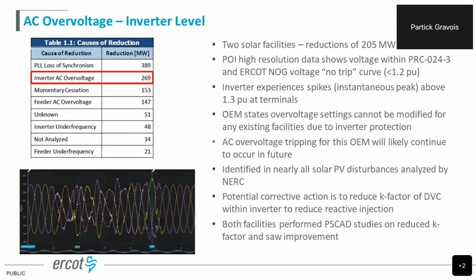The next was the inverter AC overvoltage. This one is a little more complicated to mitigate. There were 2 solar facilities, 205 megawatts and 64 megawatts, the next largest cause of reduction. So what we were seeing is the inverter protection is based on voltage at the inverter terminals. Voltage ride-through requirements are for the POI. We're finding there's a pretty large difference between the POI voltage and the inverter terminal voltage as well.